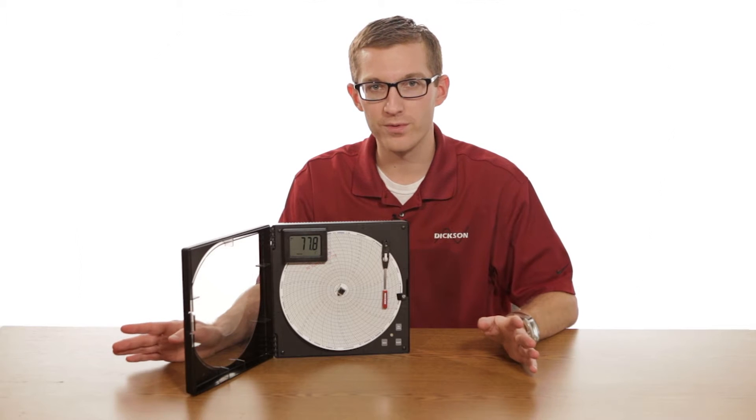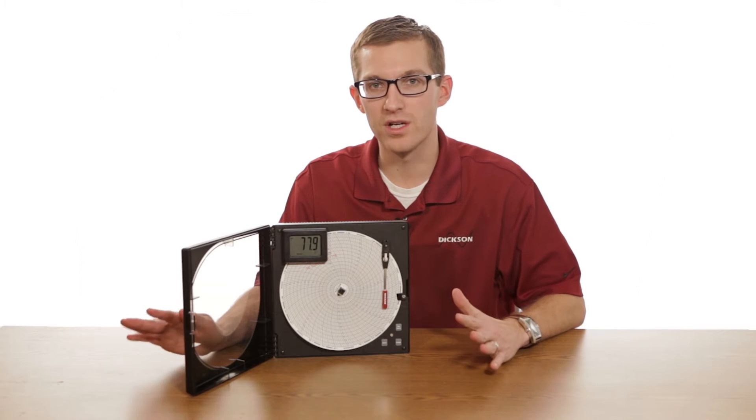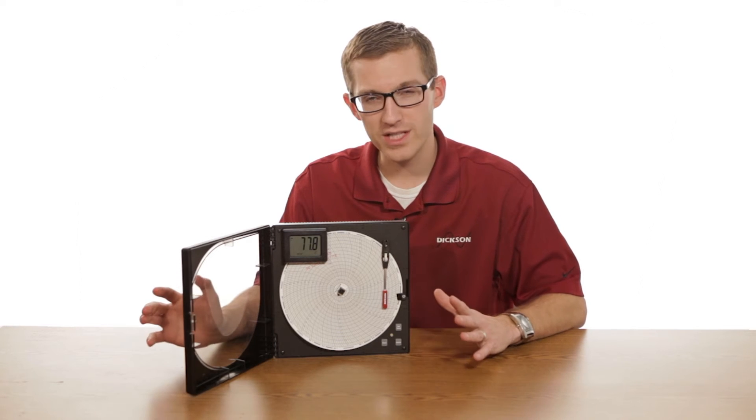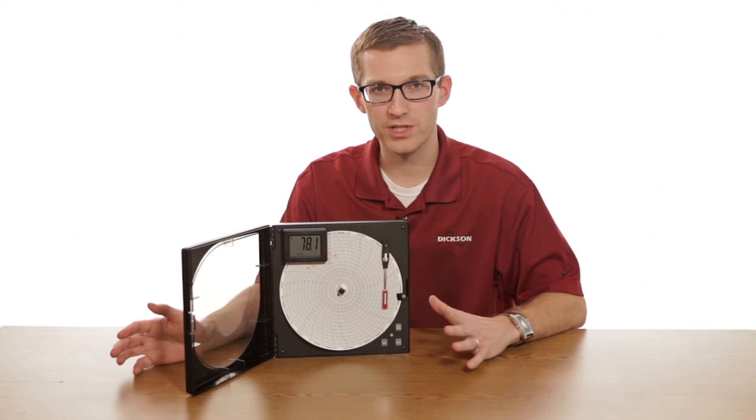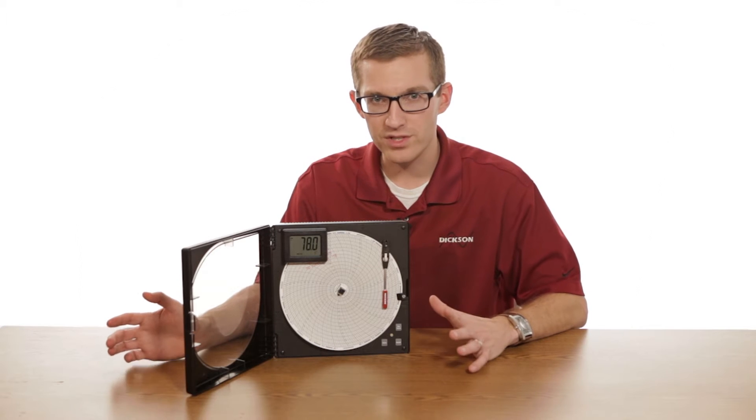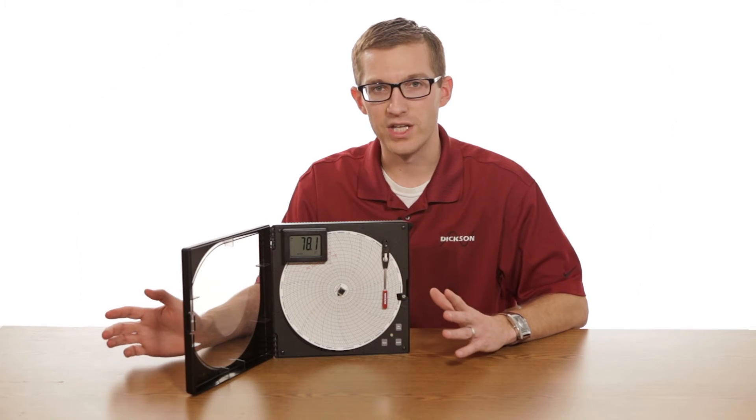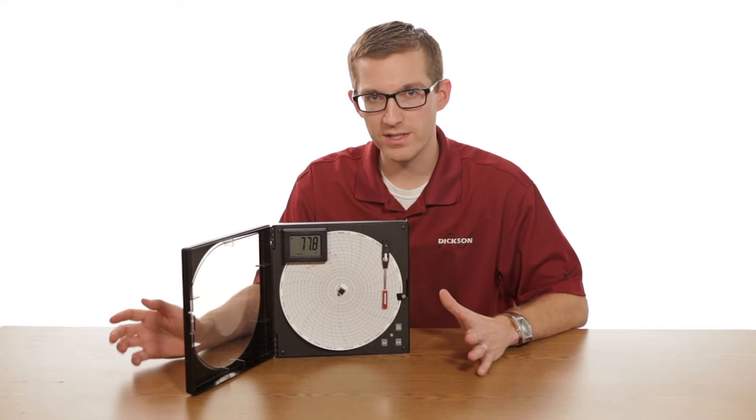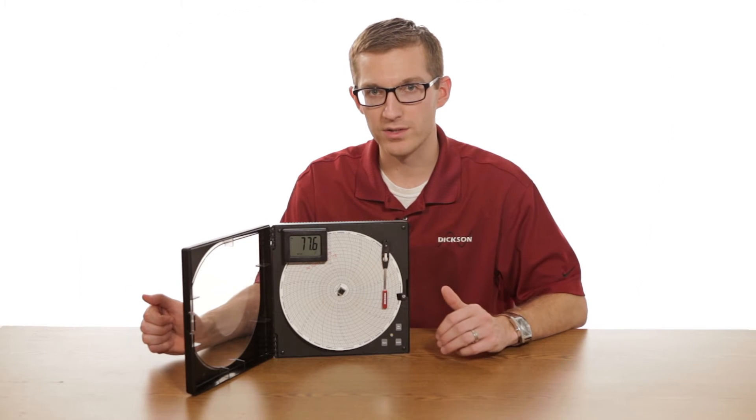It's important to note before we start this process that your unit does come completely calibrated from the factory here at Dickson and the only time we should do a calibration on a unit is after 6 or 12 months and you have a good standard that you can compare it to. Generally we say that it needs to be 4 times more accurate than the unit.